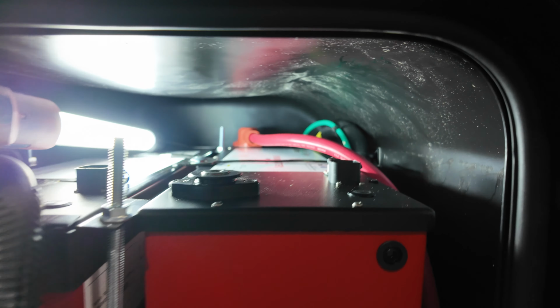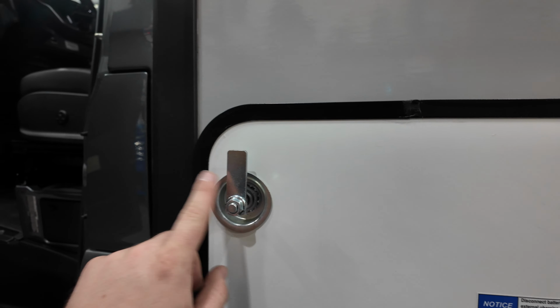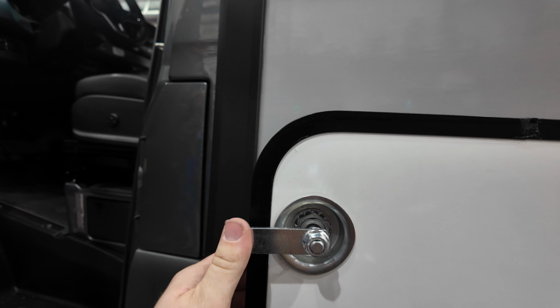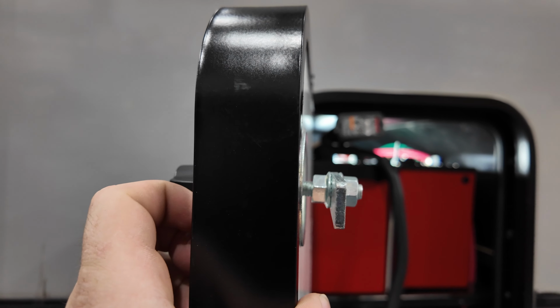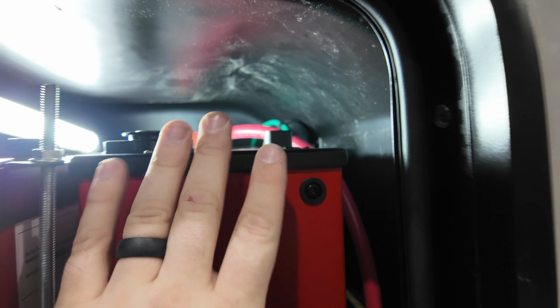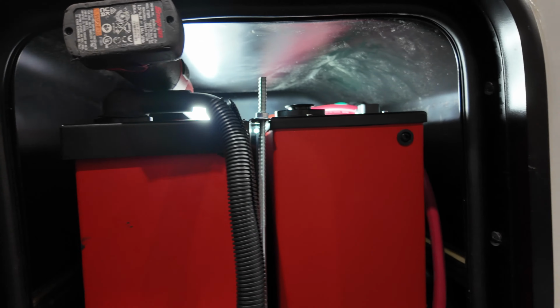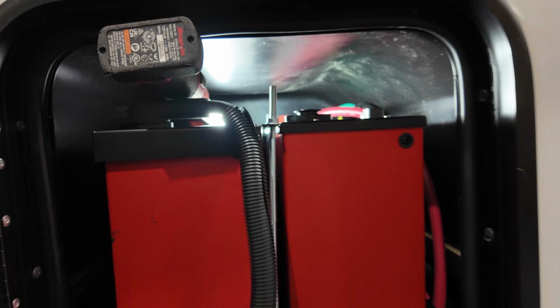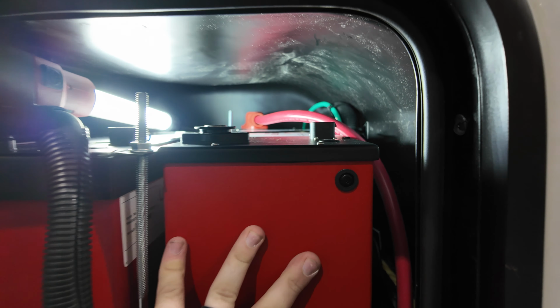The reason we need to take so much care to push those wires and get those out of the way as much as possible is because of the door latches here. This upper latch, when it turns on its side, protrudes from the back of the door. So if you're not careful and the battery is not pushed in far enough, that latch will smack the side of the battery and cause some damage, and the door won't close. So if you take care to make sure that this battery is pushed back as far as possible, you won't have any interference with the door latch.